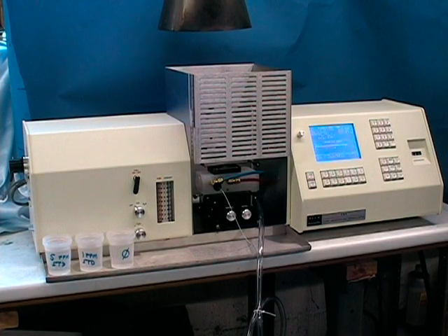Once the energy has been maximized based on the position of the wavelength and the lamp, press the escape button to exit the alignment screen, auto-zero the electronic energy signal from the hollow cathode lamp, and get to your active analysis screen. At this point, you should see a display showing approximately 0.000 absorbance units. At this point, we are ready to fire up our AA and begin our calibration curve.